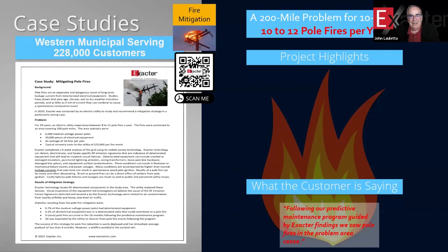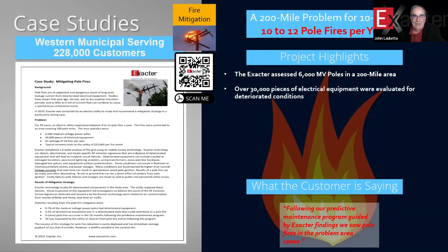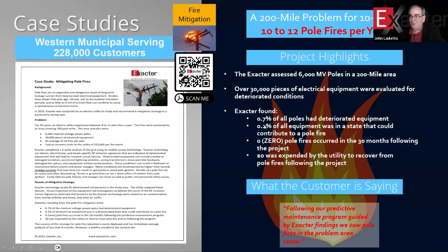And it was very specific on this 200 miles of line. So they called us in out of desperation more than anything. And so we took a look at it and we did our study. There were about 6,000 medium voltage poles in the study area. That represented about 30,000 pieces of equipment that could participate in this problem. And what we found was that only about 0.7% of the poles that we studied had a piece of deteriorated equipment that was indicated by partial discharge emission.